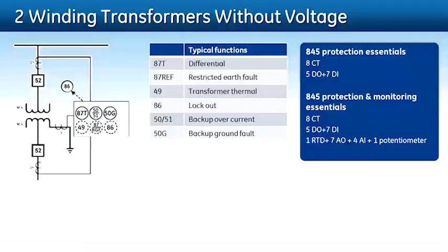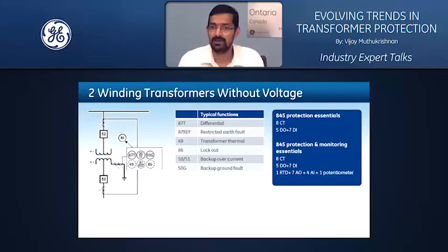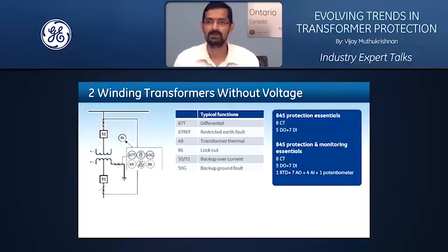The first most common application of transformers you see is the two-winding transformer application without any voltage. This is more common probably on medium voltage applications and probably a little bit around sub-transmission applications, where you pretty much would use the core functionalities of a transformer protection, be it differential protection, restricted ground fault, simple thermal elements, a lockout protection with an overcurrent backup and ground fault backup elements. This is what a simplified transformer application can contain. In the case of our Multilin 845 device, you can easily achieve this with an 8CT analog subsystem and a single combo I/O card that has 5 outputs and 7 digital inputs, which can meet this particular need in a simpler manner.